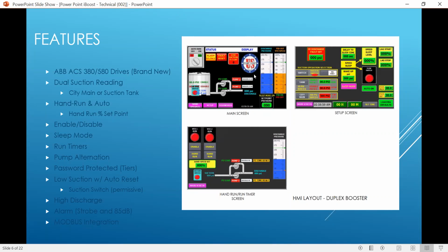On the alarms, we have the standard alarms, which are basically your low suction, your no flow alarm, your high discharge, and the alarm also has a strobe on top of the panel. And we also have the Modbus integration if you need that. So with your building communications, we're pretty good about that. We can pretty much match any customer's needs there. You just have to give us a heads up in terms of what you're using. We like to use the Modbus just because it's easier and a little less expensive. There are obviously a couple different settings, and Kevin, I don't know if you want to talk about that for a sec, as far as how we interface with the building.